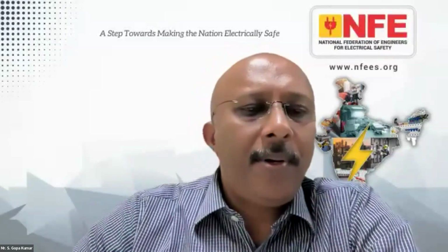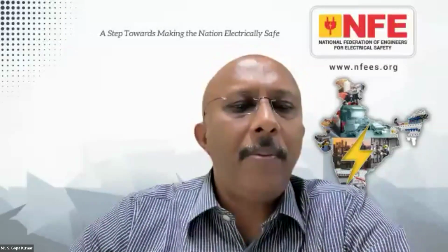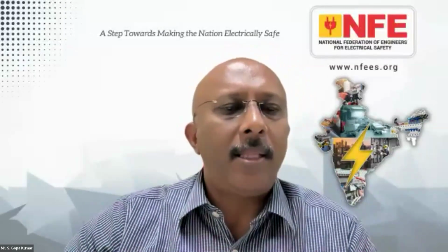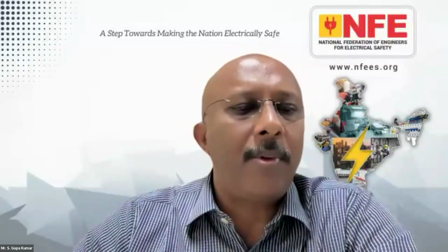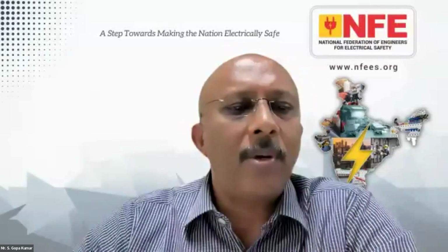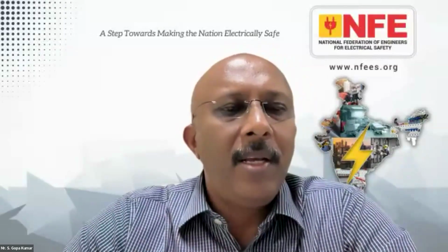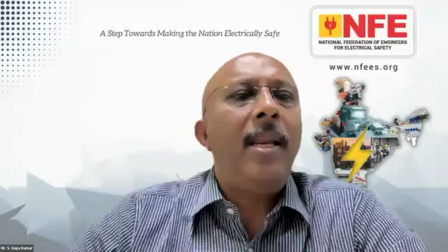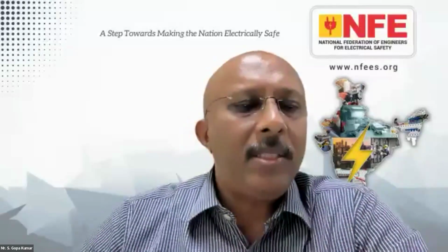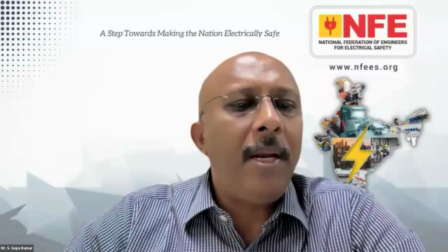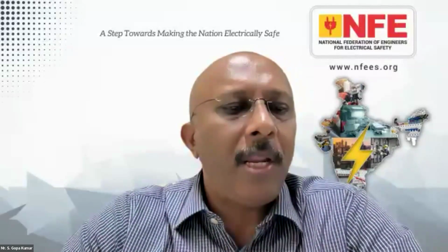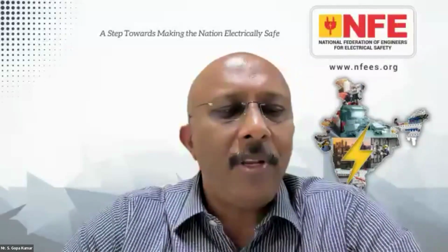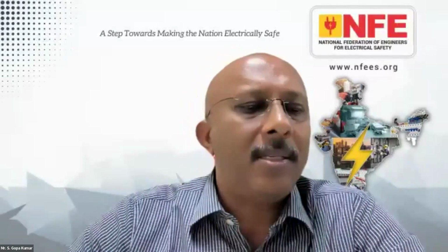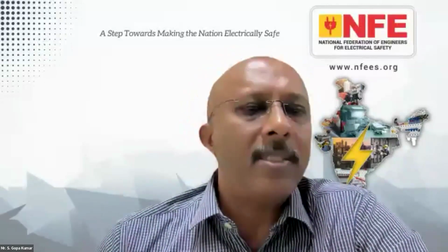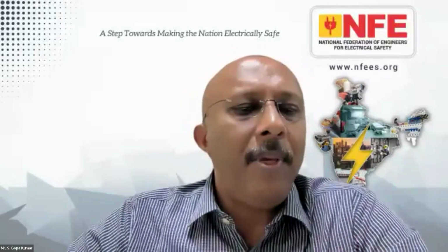Basically we should look at two subjects. One is protecting the people in the lift car, where lights and other single phase 230-volt electrical equipment are used. For that, a 30 milliampere RCD is a part of the lift as a machine, so it has to be built in by the lift manufacturer. Whereas once the entire lift is connected in a building, the circuitry supplying power to the lift should have basic protection and fault protection. In case of an earth fault on the lift, there should be a mechanism to automatically disconnect. For that, we do the fault loop impedance test or use a 30 milliampere RCD type B, since VFDs are there in the installation.